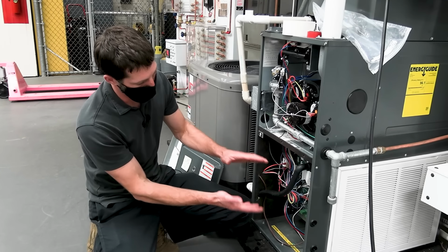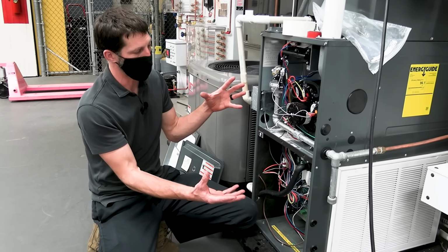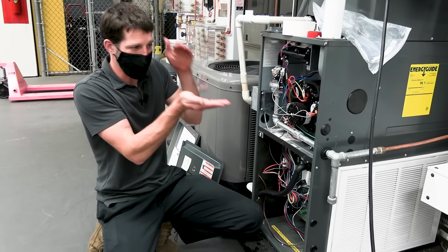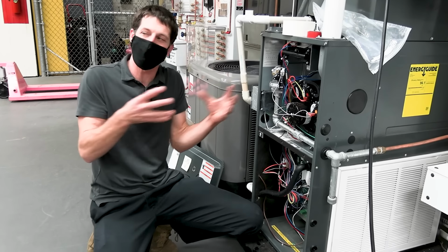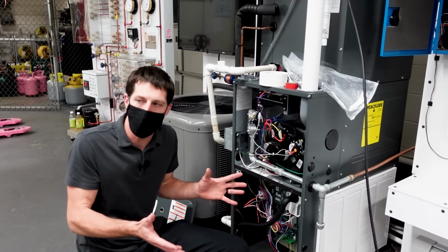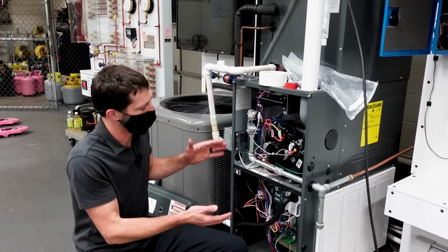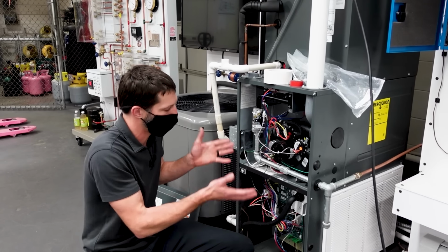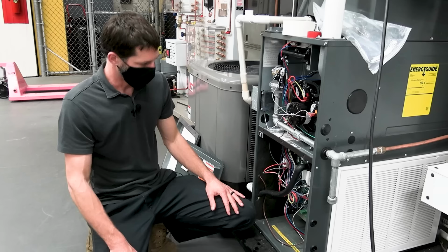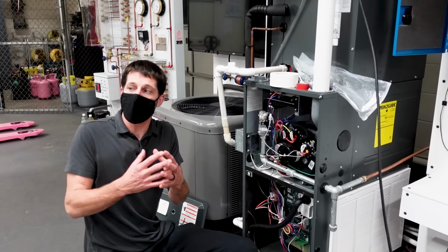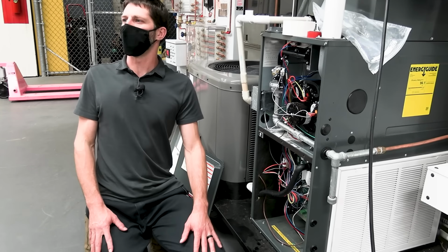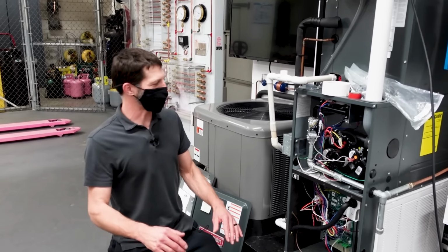So the control board is going to be able to get the extra efficiency, say from 90% efficient to 96% efficient, it's kind of getting that out of the ECM blower motor and the airflow, so the heat exchange between the primary and secondary heat exchanger and the variable speed blower motor. So I call it a 7-step sequence of operation. Some people call it 6-step. You kind of just make up your own thing. Once you're comfortable with that, you just teach that.